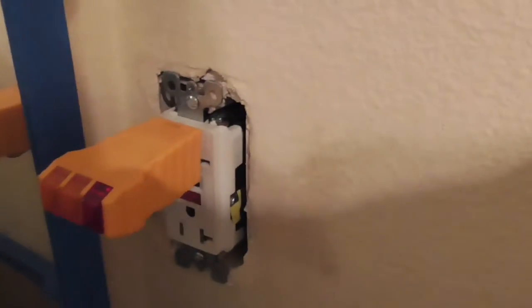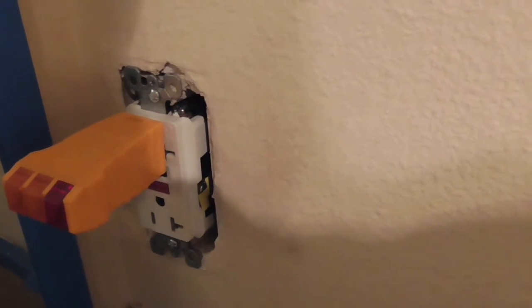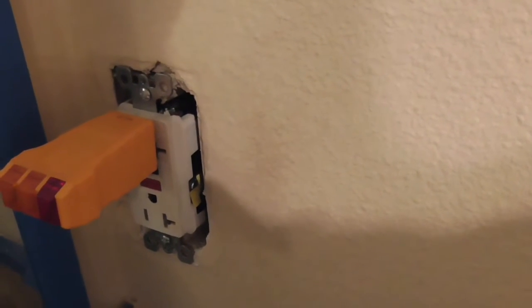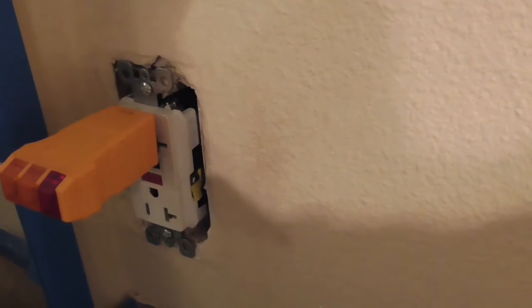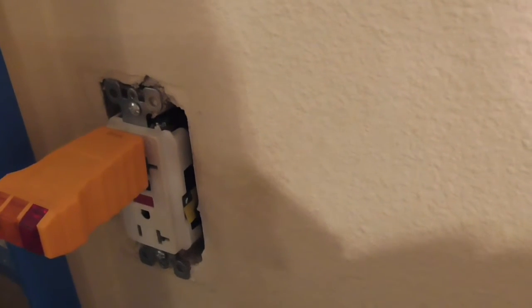Now you want to check it with a meter, it's really smart to check it with a meter. I'm going to plug this in just to see what happens. No lights came on, there's no power on this thing. But you do want to be really careful when you pull this thing out, put a meter on there or a light probe. Don't use those things that when it gets really close will tell you if there's power in the wire. You could kill yourself with some of those things because they might not be accurate. So you do want to use a voltmeter to show if there's power on there or a little light tester. But I'm going to unscrew the two screws now at the top, pull this thing out, and reverse the wires, and then we'll see if it fixes it.